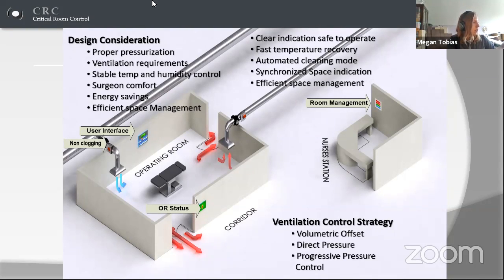So they'll have the two variable air volume boxes, and then they'll have a pressure monitor on the outside of the space. You can see the status of the room from the outside without having to go in if the room is in use. And within the room, there'll be another monitor that'll show all the people within the operating room whether or not the pressure in the room is good, what your temperature is, where the humidity is, and it allows you to adjust set points from there.